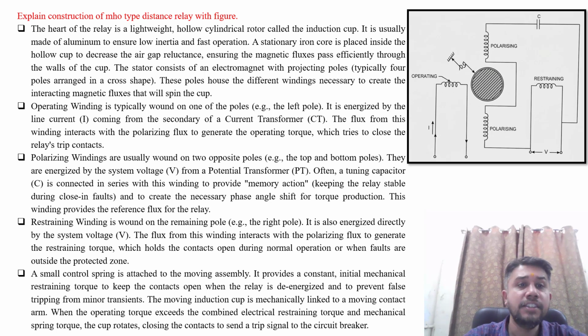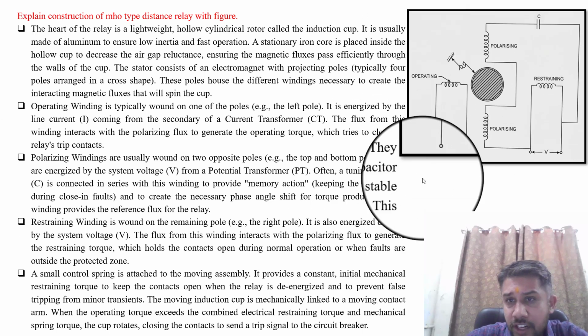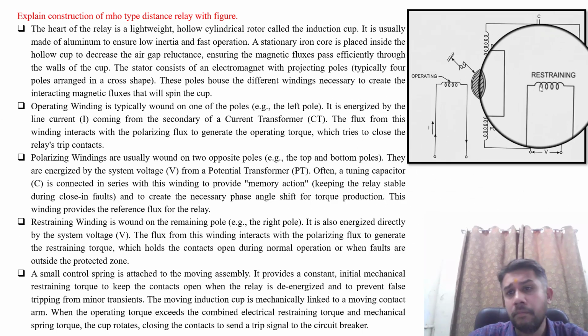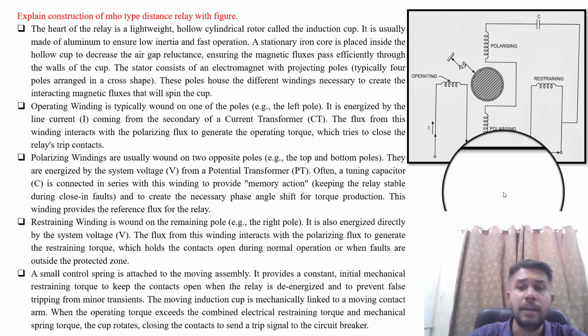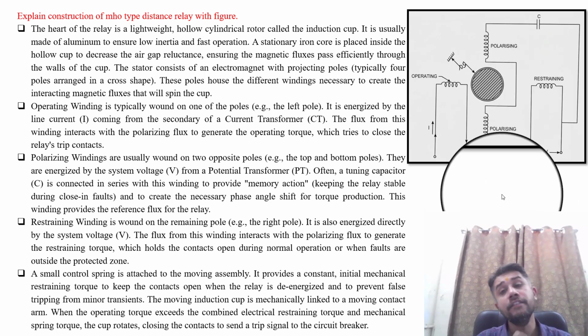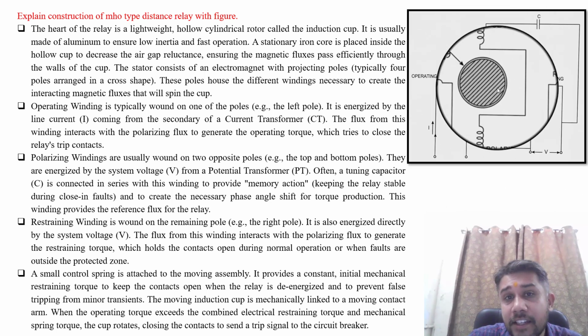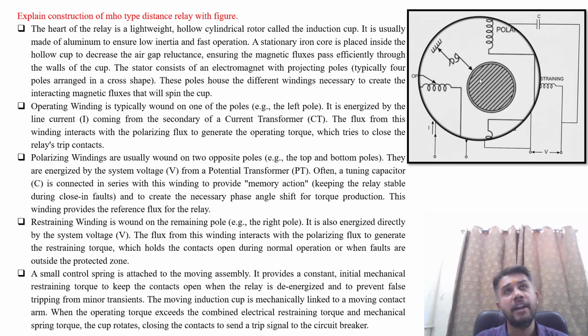Explain construction of mho type distance relay with a figure. So you can visualize in the figure, this is the internal construction of a mho type relay. The heart of the relay is a lightweight, hollow, cylindrical rotor. This is called the induction cup. It is usually made up of aluminum to ensure low inertia and fast operation.